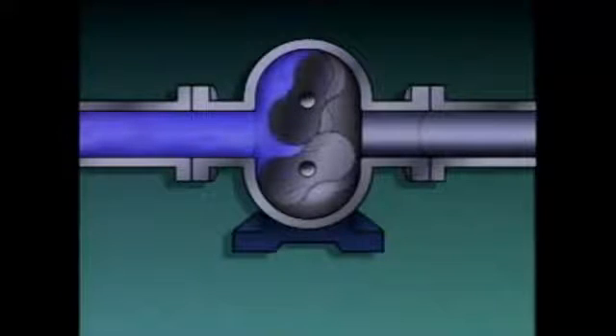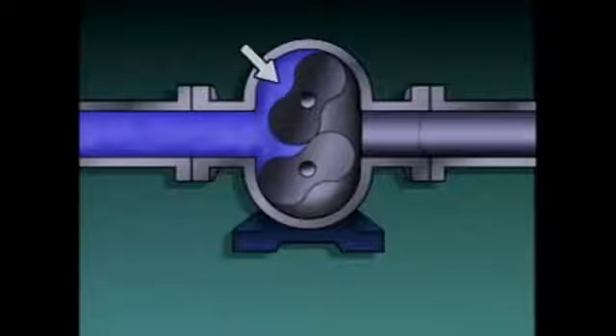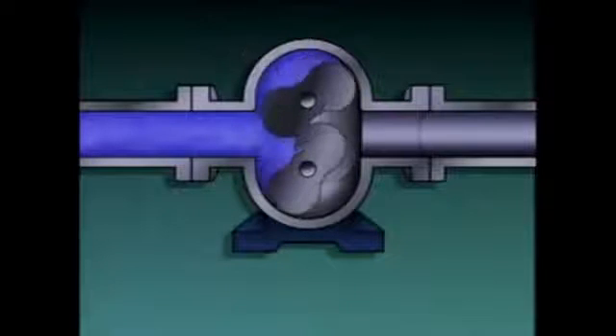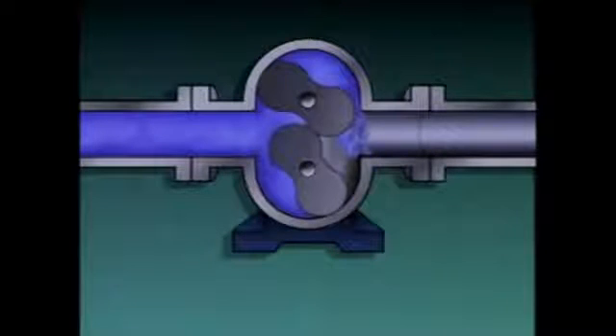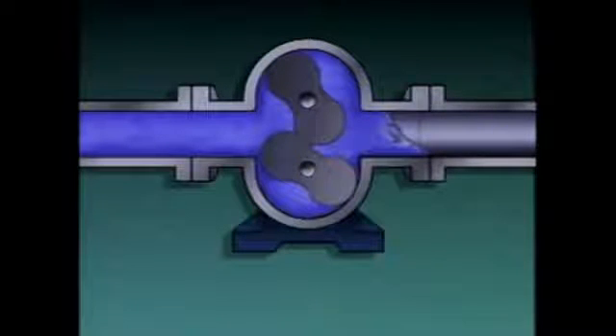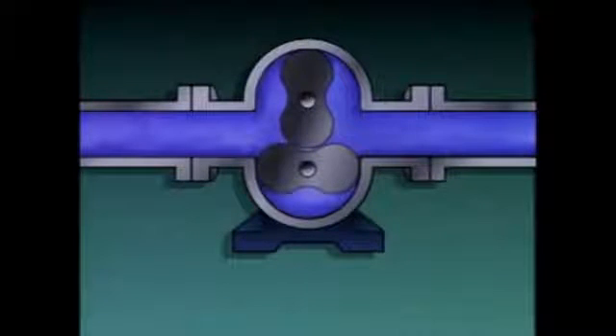During operation, the lobes rotate and draw in process liquid through the suction of the pump. As the lobes unmesh, gaps are formed and liquid is drawn into these gaps, then trapped in the spaces between the lobes and the casing. As the lobes continue to rotate, the liquid is moved along to the discharge of the pump, where it's forced out of the pump and into the discharge piping.